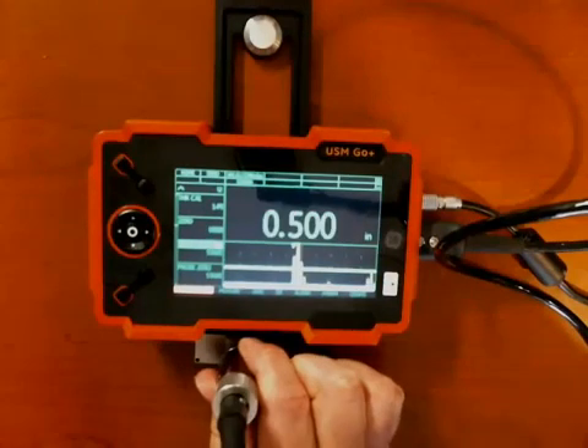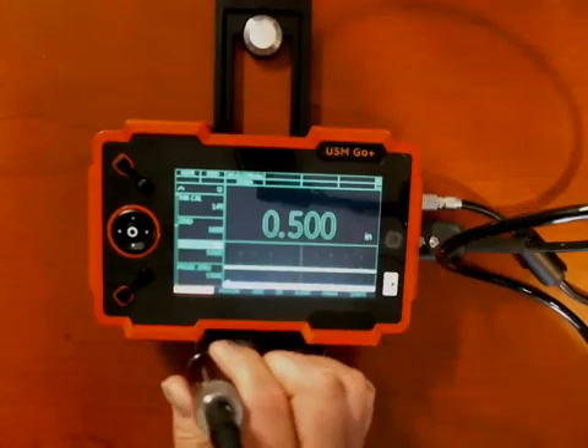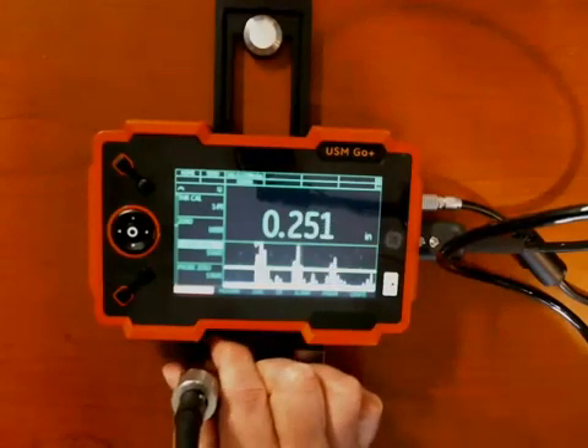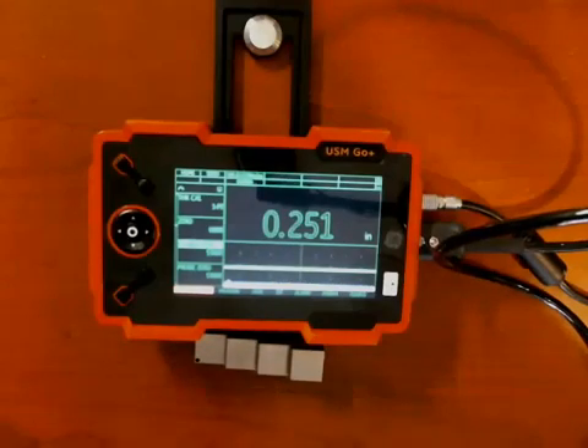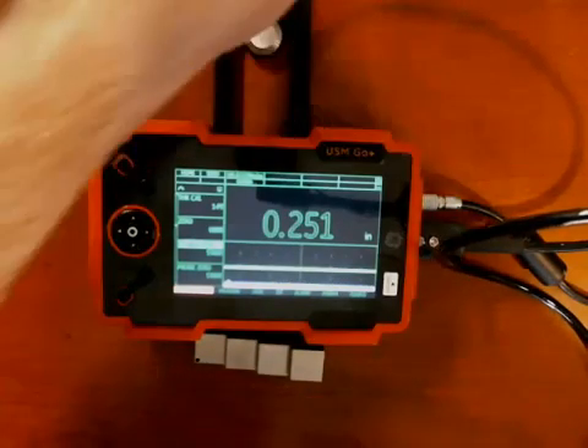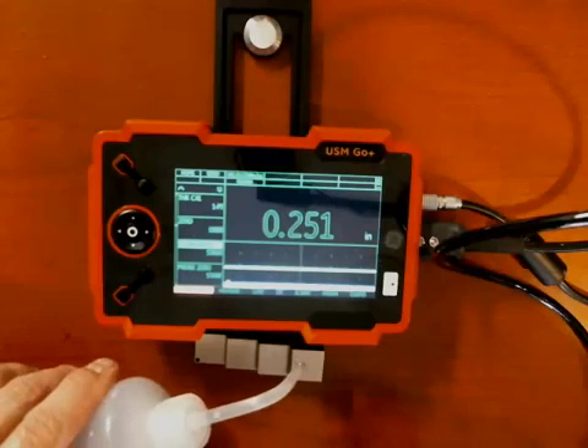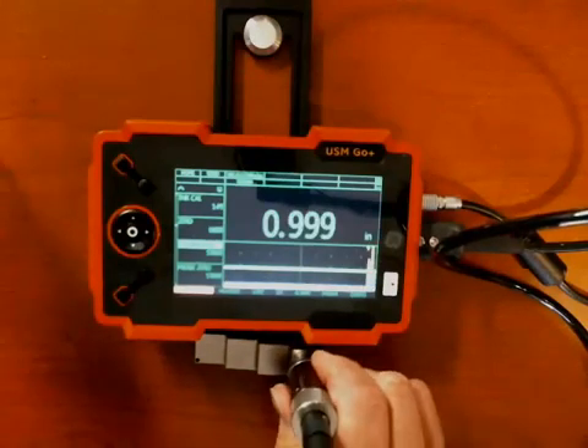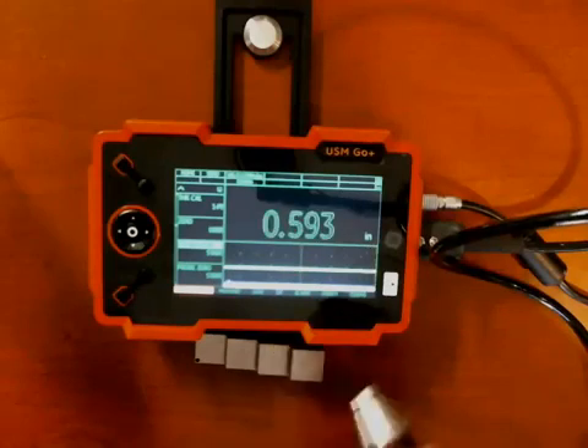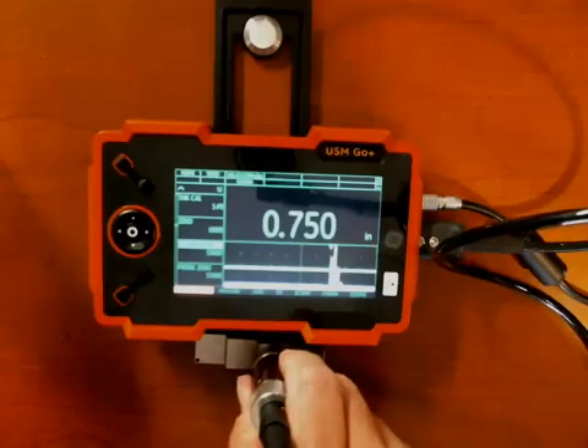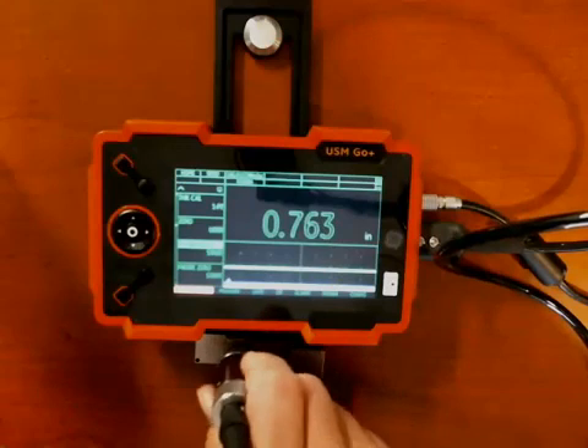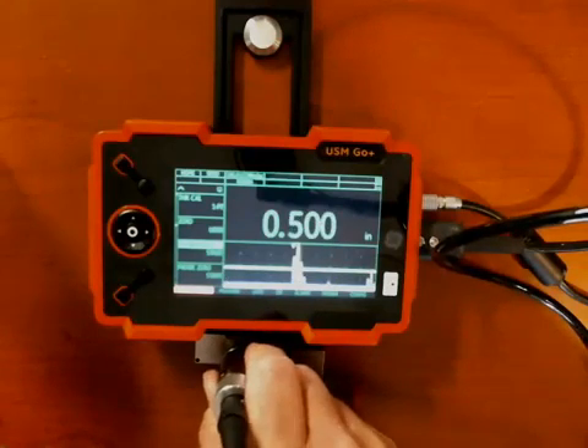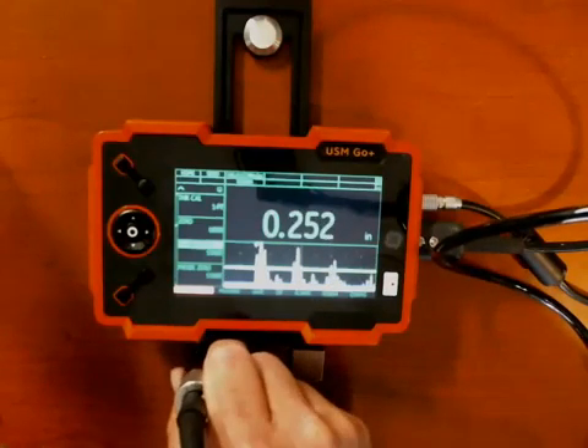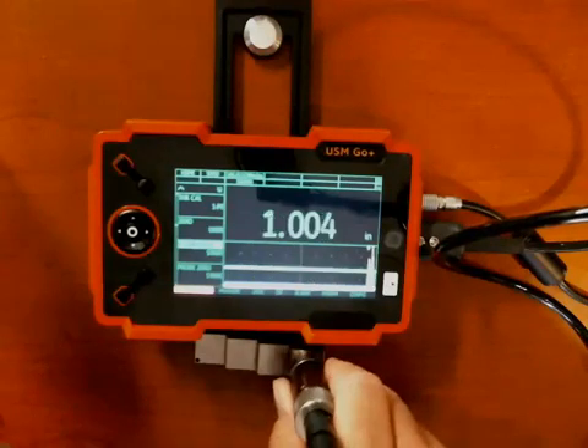Go to the 1/2 inch step, 500, go to the 1/4 inch step, 251. So I have a little bit of dirt and dust on my block here, so I might be off by a thou or two. And there's 1 inch. So I'm a thou shy at an inch. 750, 3/4 inches dead on. 1/2 inch, 1/4 inch, 1 inch. Okay, so that's the calibration process.